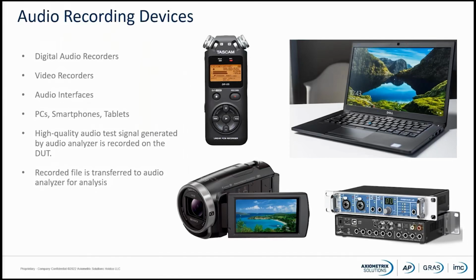process for testing. To test the record signal path, we first play the stimulus signal from the APX generator into the DUT while recording it onto the DUT's file format and media. Next, we move the recorded file to the test system's host PC and use file analysis in APX 500 software to analyze the recorded file.